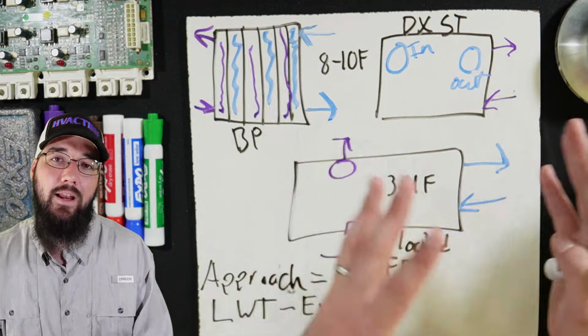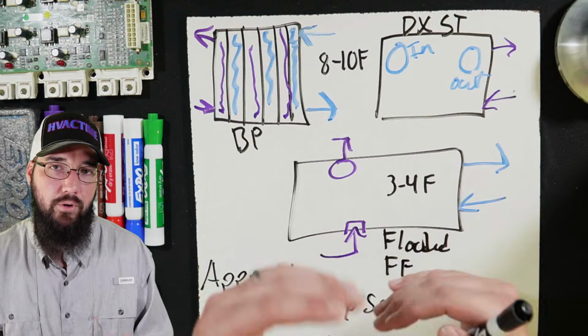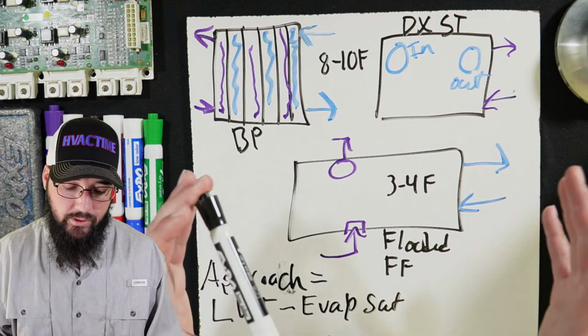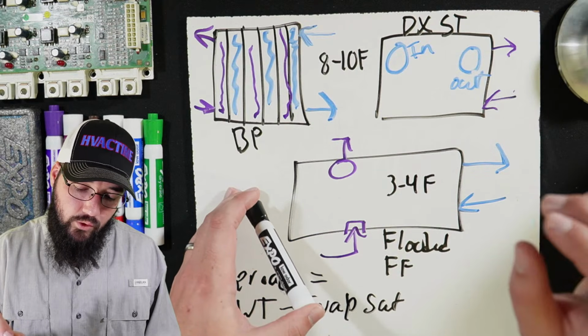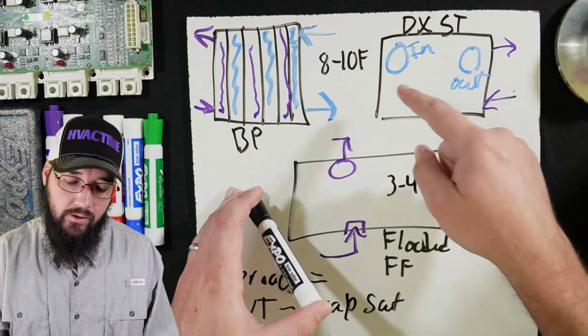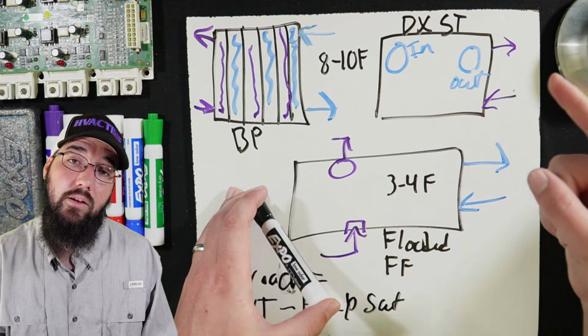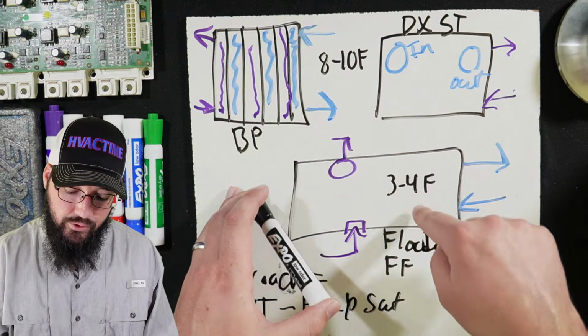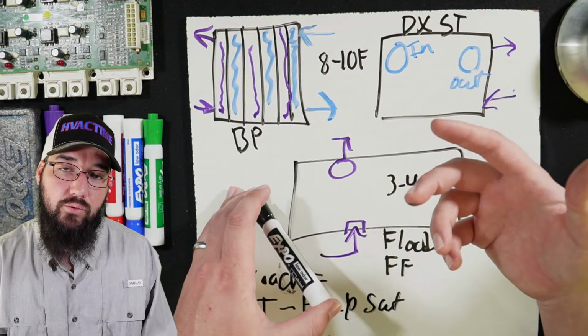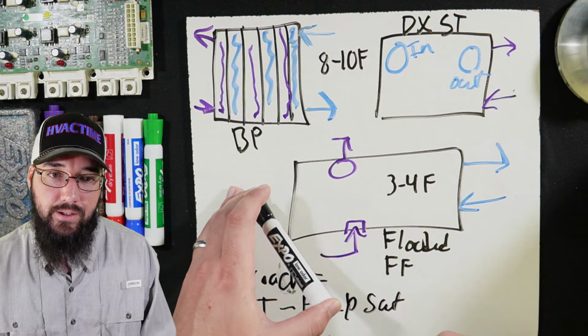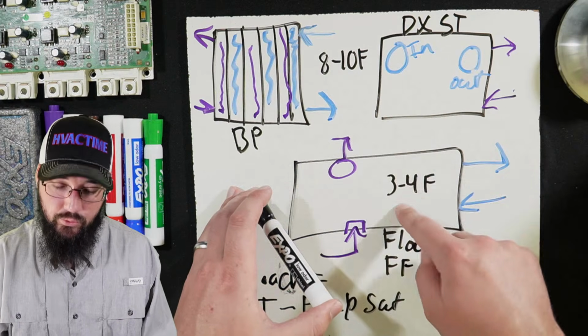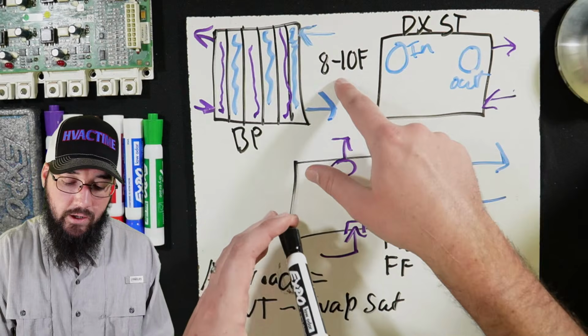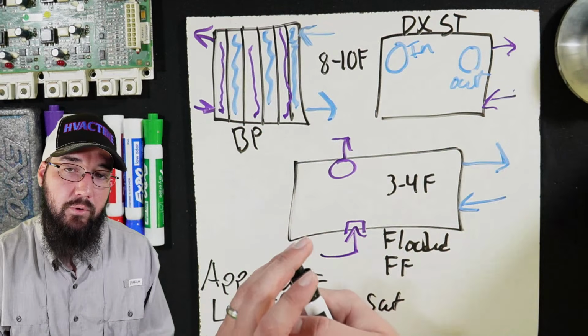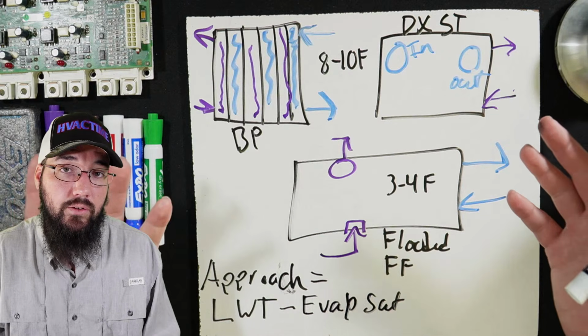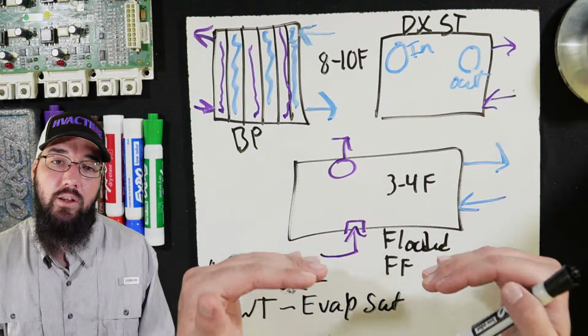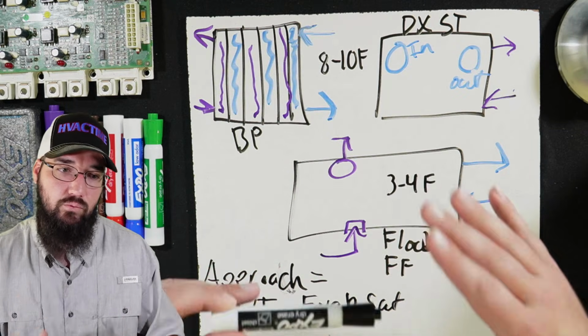I'm sorry, I'm trying to high level this. Again, if you really want a proper explanation where I break this down, the certification program is your place for that. Okay. So good GPM at design, this is what you would expect. As we unload, these numbers should drop. So if I have a compressor running at 50% capacity, then I would expect this number here to drop roughly accordingly. So that may mean I only run 5 or 6 degrees at minimal capacity. This one may only run 1 or 2 degrees, if that. So these will significantly reduce as the machine unloads, and there's no direct blueprint there.